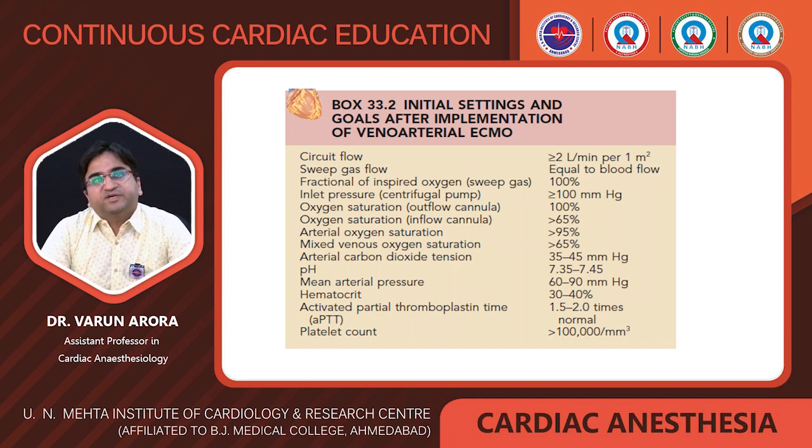So circuit flow can be set at more than or equal to 2 liters per minute per meter square. Sweep gas flow equal to the blood flow. Then FiO2 of 100%, inlet pressure of centrifugal pump more than or equal to 100 mm mercury.